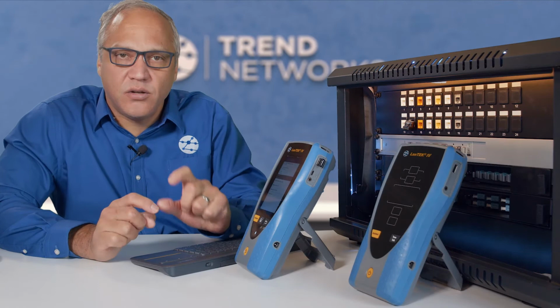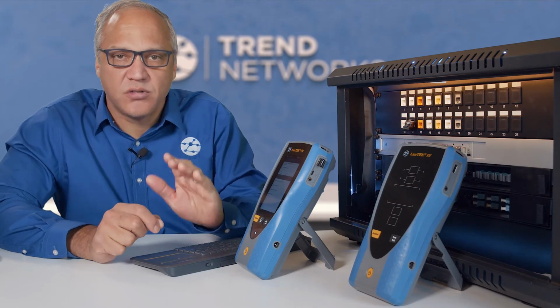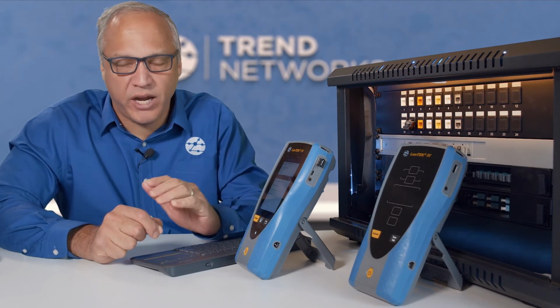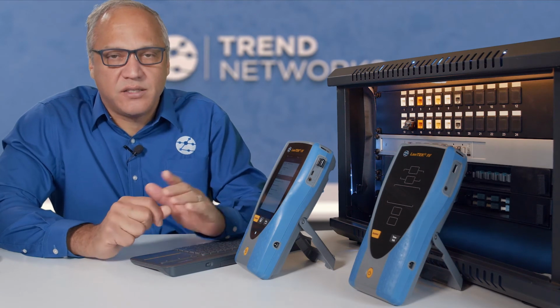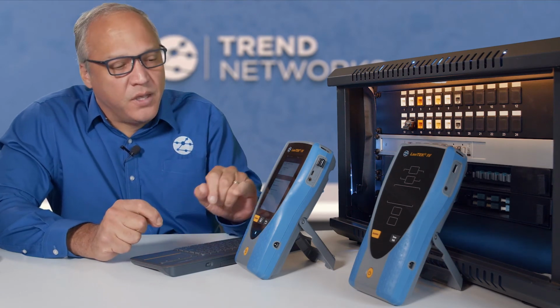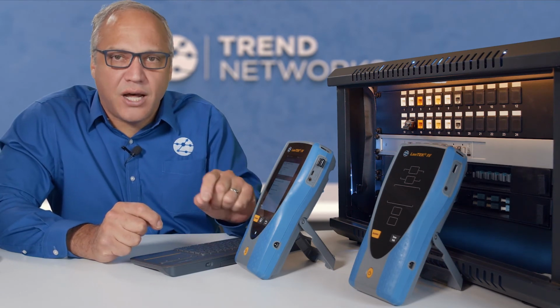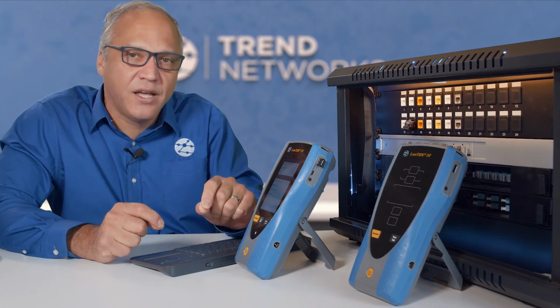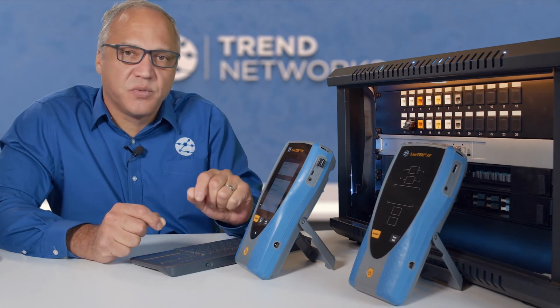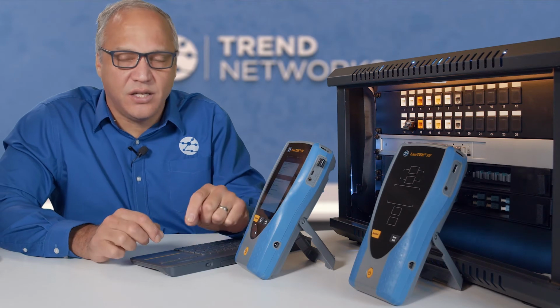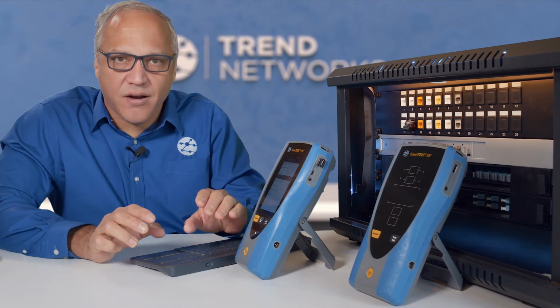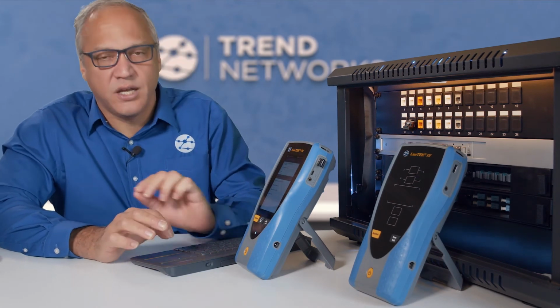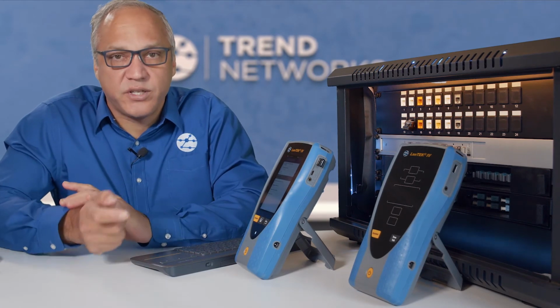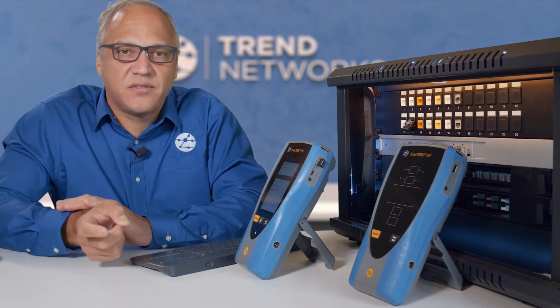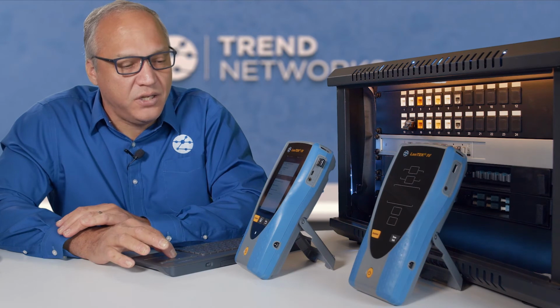So this is still going to measure those parameters. So we always measure every parameter with every auto test, and that does not increase the test time. But what we're doing is not running a pass-fail check against, in this case, resistance unbalance, TCL, and ELTCL. Those measurements are there. We're just not going to do a pass-fail check, which means later on, though, we can recertify and do a pass-fail against those measurements in the future if we need to.